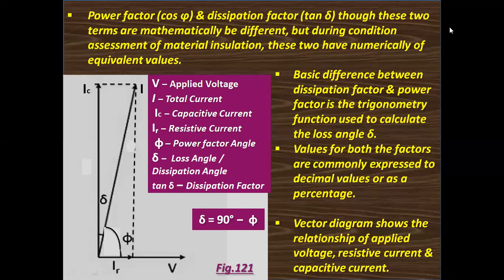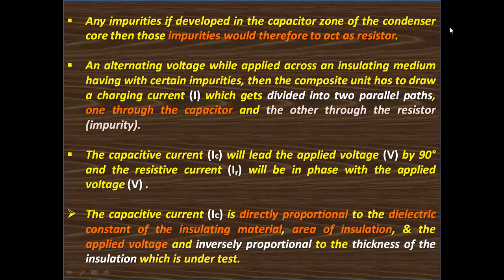Now, the vector diagram shows the relationship of applied voltage, resistive current, and capacitive current. If there is no pollution or defective items or moisture, then I is in line with IC. But due to some impurities, IR deflects I by a certain angle, that is delta. Any impurities, if developed in the capacitor zone of the condenser core, would act as a resistor.